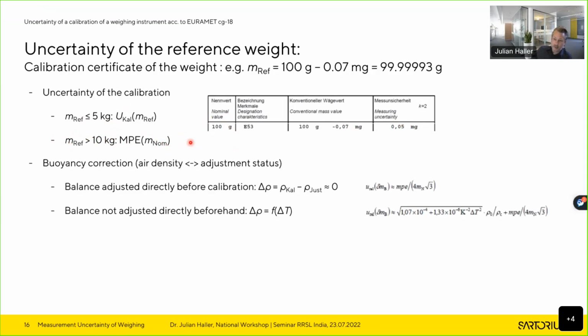The next thing is quite complicated. You have to take into account, as an uncertainty contribution, a possible buoyancy correction. This is due to the fact that if you adjust the balance directly before the calibration, then you can assume that the air density at the calibration is the same as the air density at the adjustment, because you do it directly afterwards. But if you do not adjust directly before the calibration, you have to take into account that the air density might have changed between adjustment and calibration.